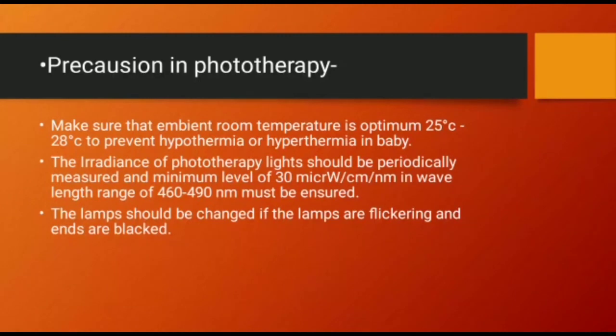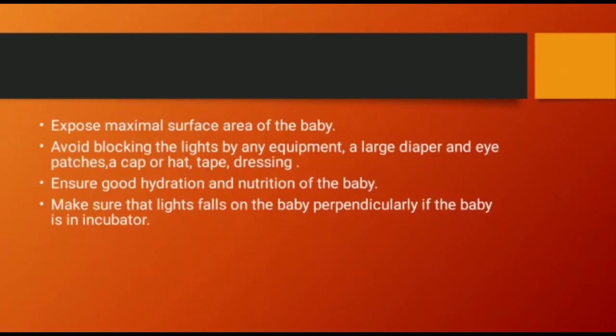Precautions in phototherapy: ensure that ambient room temperature is optimum at 25 to 28 degrees centigrade to prevent hypothermia or hyperthermia. The irradiance of phototherapy lights should be periodically measured, with a minimum level of 30 microwatts per centimeter squared per nanometer in the wavelength range of 460 to 490 nm. Change lamps if they are flickering or ends are black. Expose maximal surface area of the baby and avoid blocking the light with equipment, large diapers, caps, or dressings.